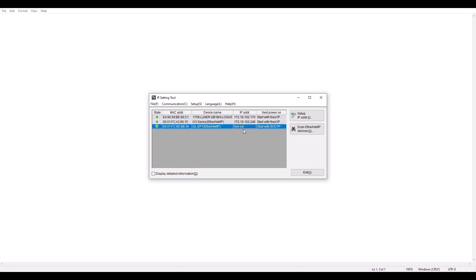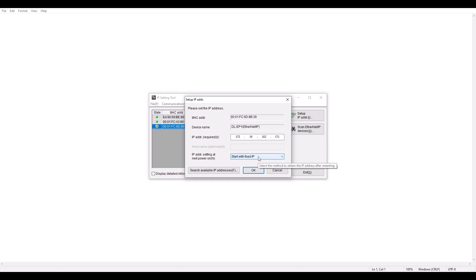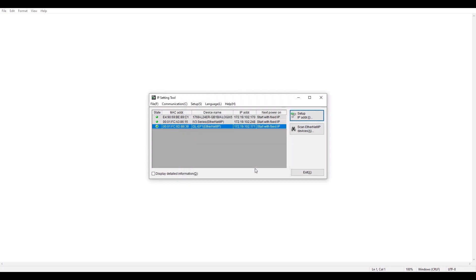So I'm going to click on my CL-EP1 and hit Setup IP Address. And for this one, I'm going to set it to 172.19.102.171. And this selection right here, make sure this says Start with Fixed IP. So once I hit OK, now the CL-EP1 will have that static IP address even after a power cycle. And you can see that is successfully set here.